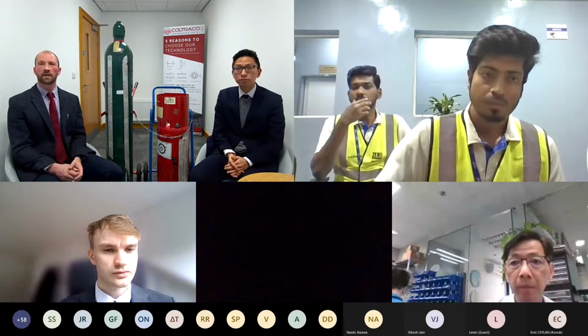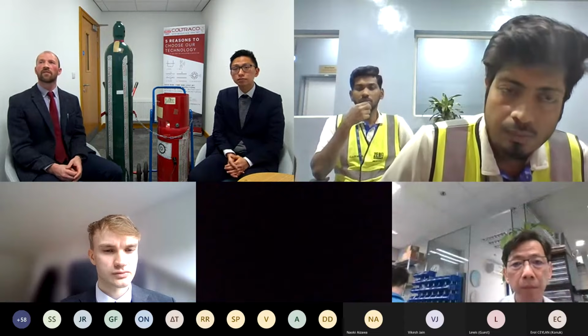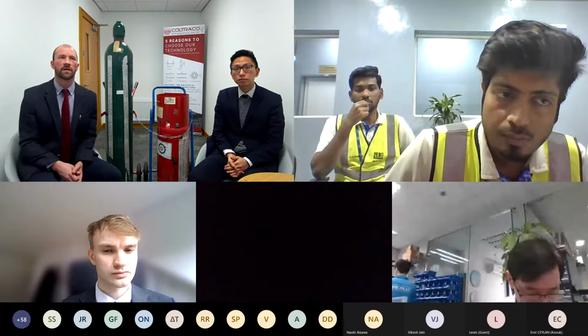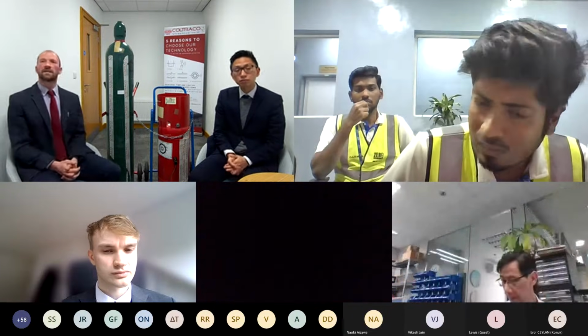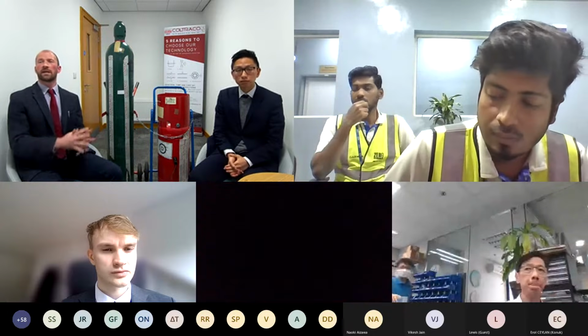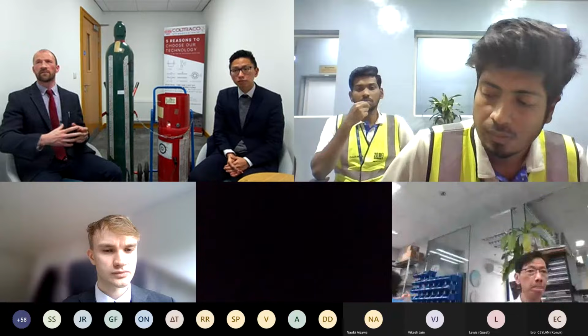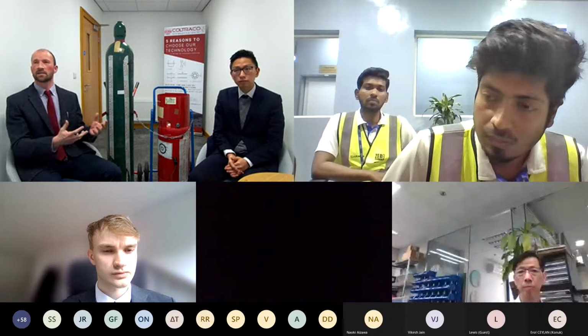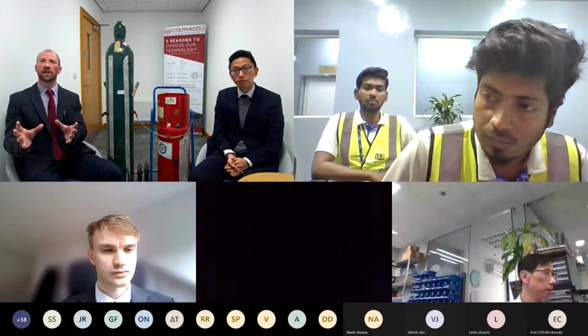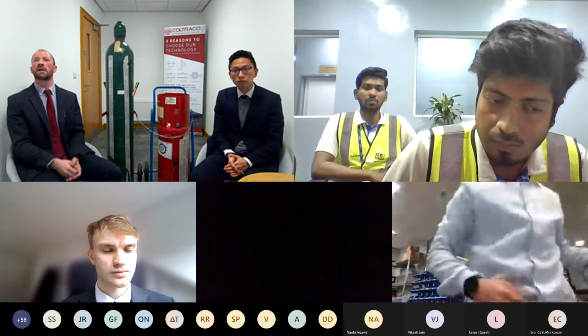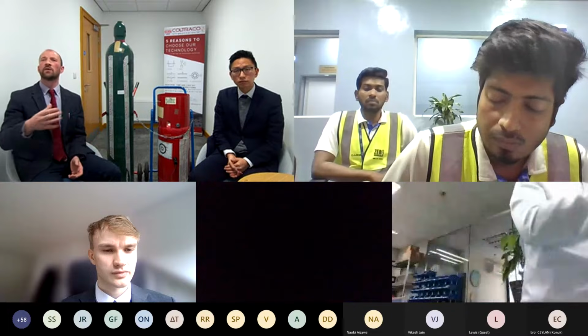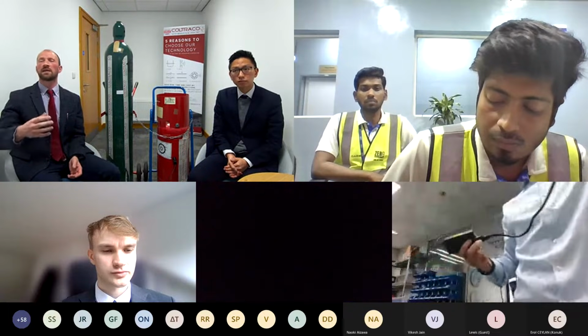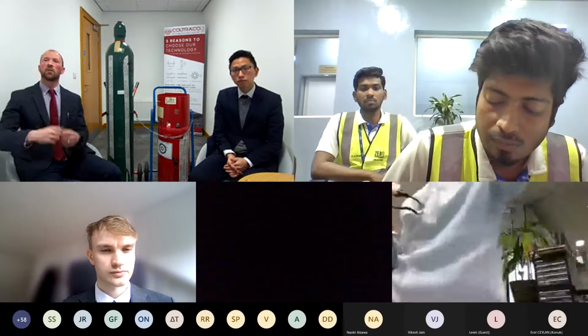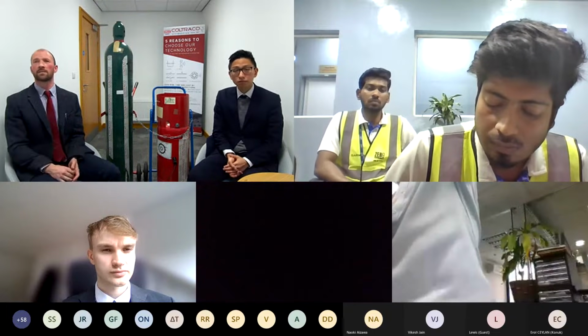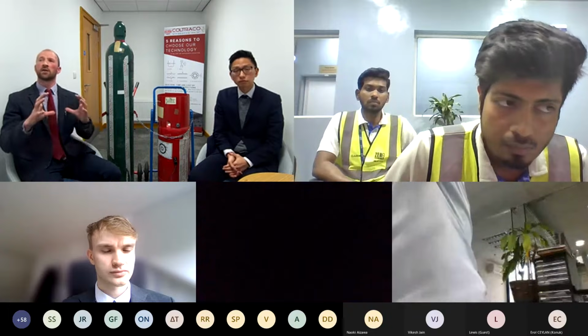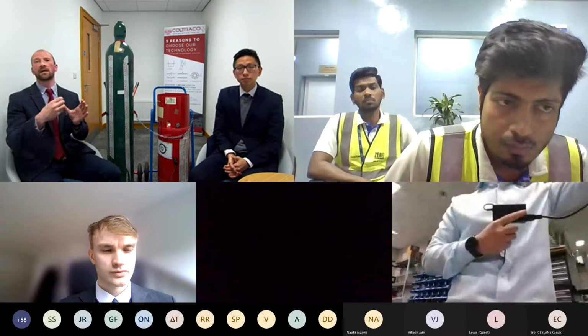Just quickly. Yes, very quickly, we've got the Permamass Featherweight, which is due to be available very shortly. This device is a continuous monitoring unit. It connects to a bank or row of Inergen systems, as well as other systems such as CO2 and NOVEC, but it's very suitable for Inergen systems, IG541, for example. It will continuously monitor the weight of these cylinders, and if there's any change in weight, the unit will alert you. And it's accurate to 100 grams. So if there's a 100-gram change in your cylinders, the unit will notify you that that cylinder is leaking. It'll tell you by how much.